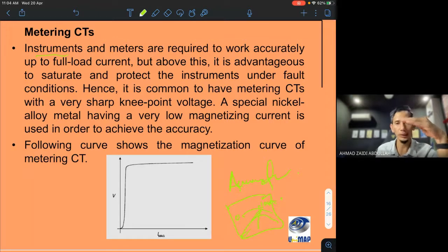Let's say full load is 100 amp. Let's say there is an overcurrent, overload. So the current flowing into your project or your design is more than 100. So how does the meter show it? Because this meter is only capable of up to 100 amp. Suddenly it has 200 amp. So that's why you have to saturate and protect the instrument.